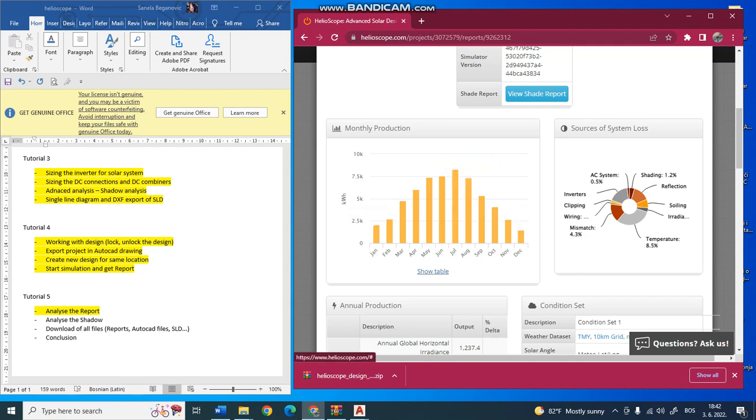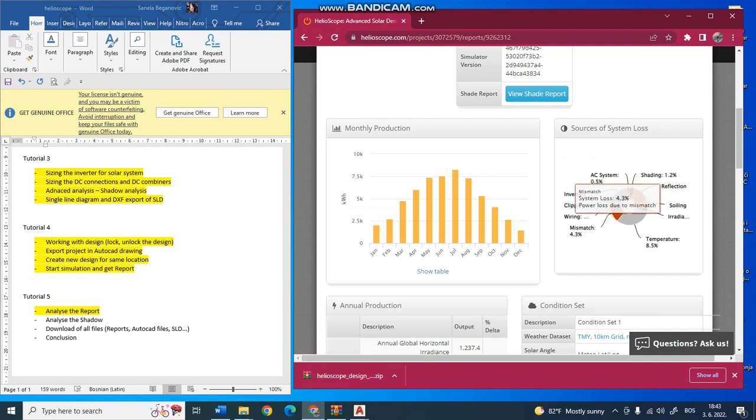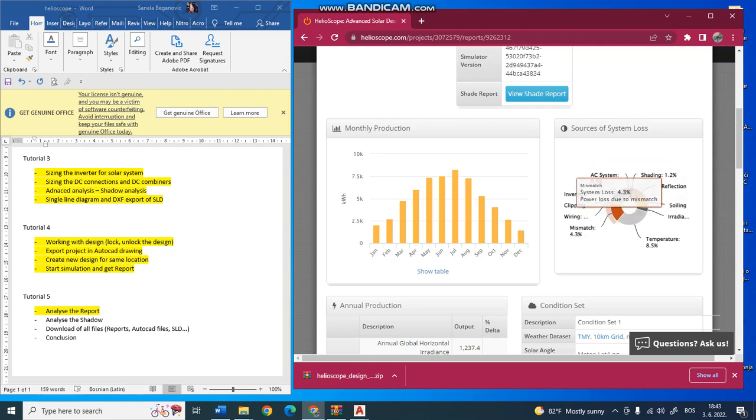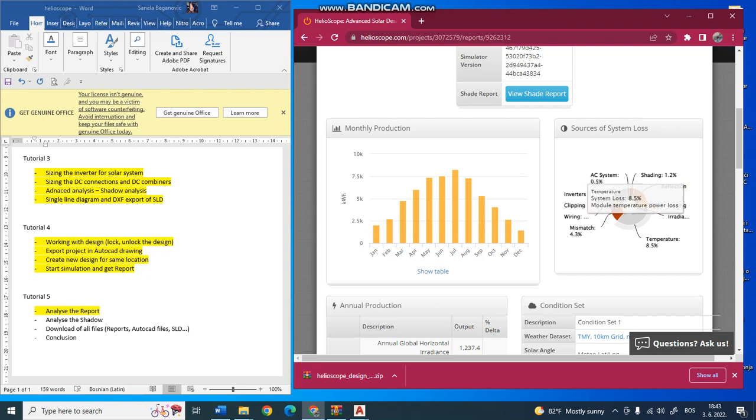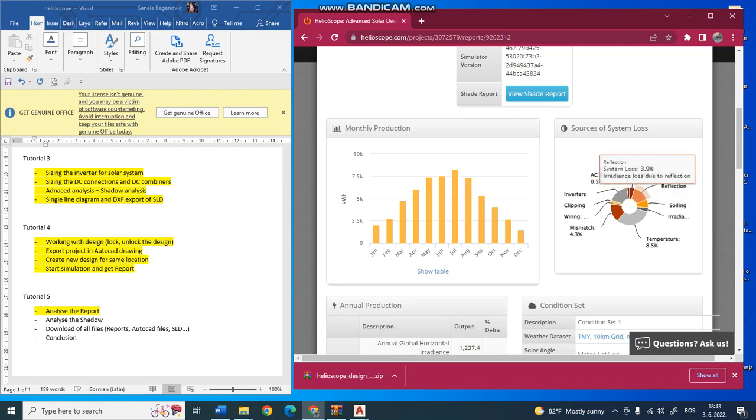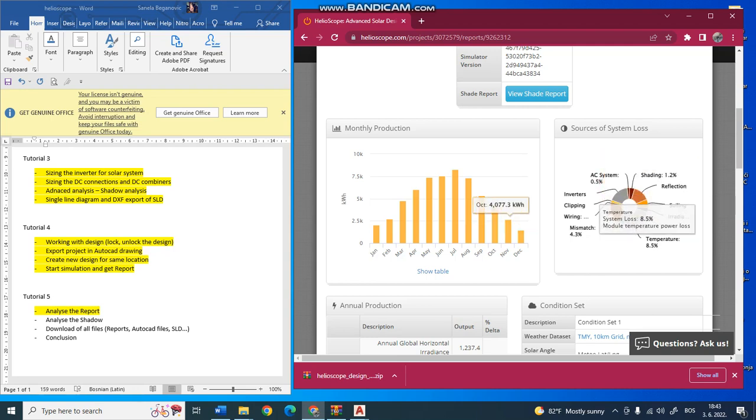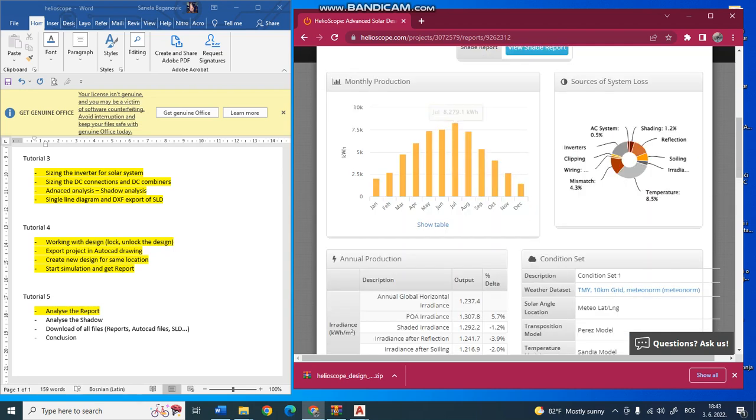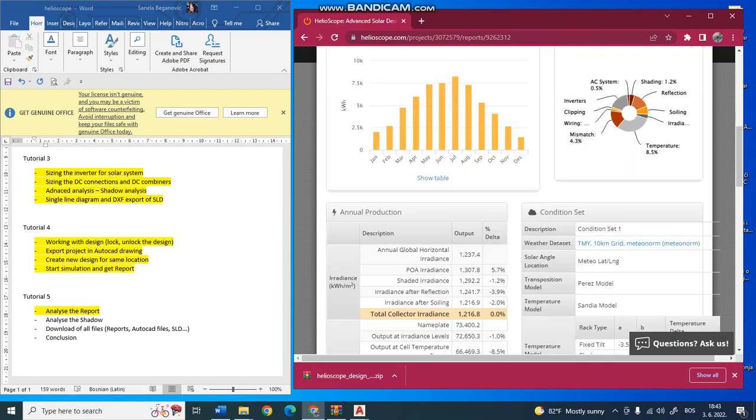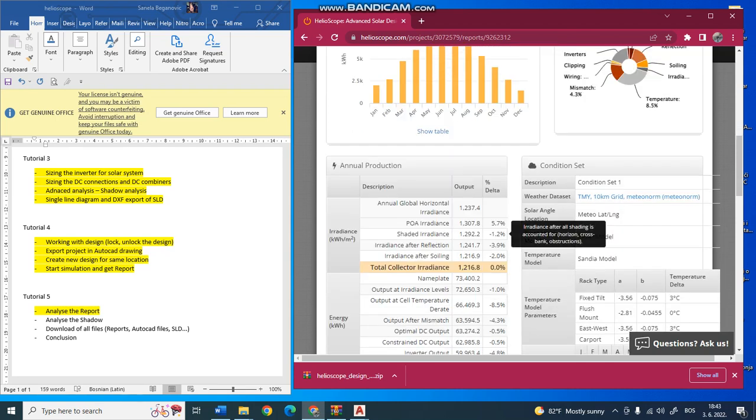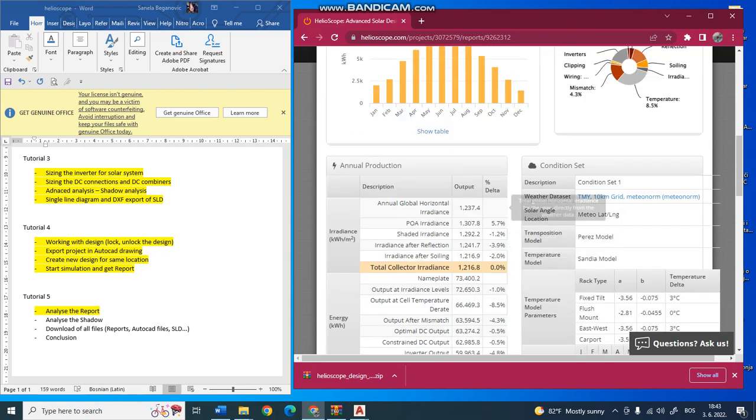You can also show this table showing sources of system losses. You see these are some losses in our system: 4.3% because of mismatch, 8.5% because of temperature and module temperature power losses, 1.2% for shading, 3.9% for reflection, and so on.